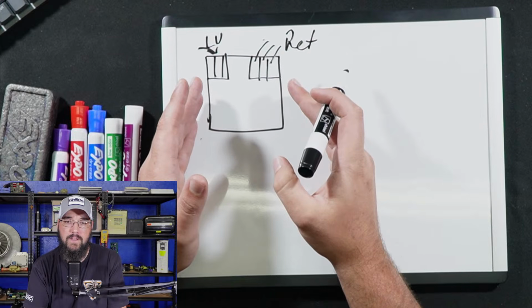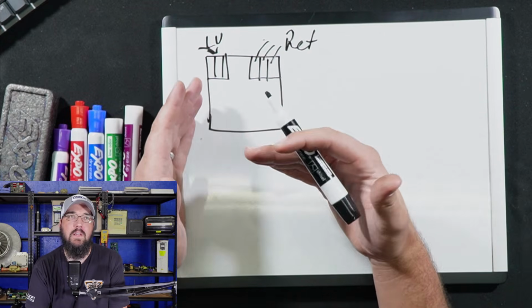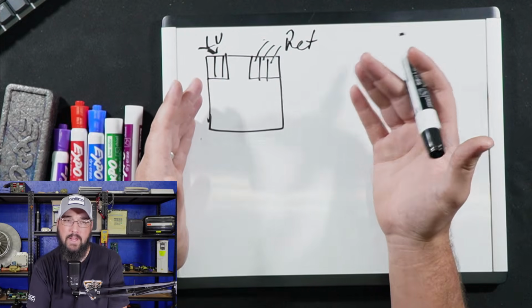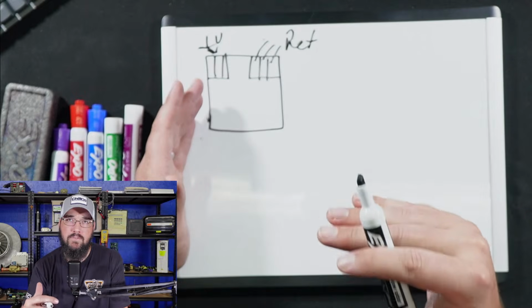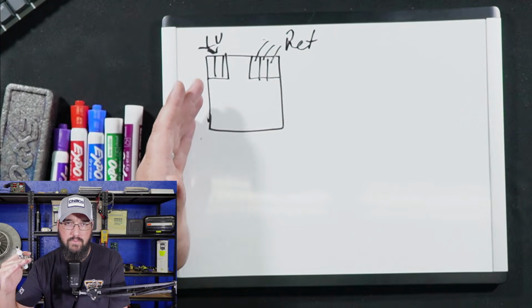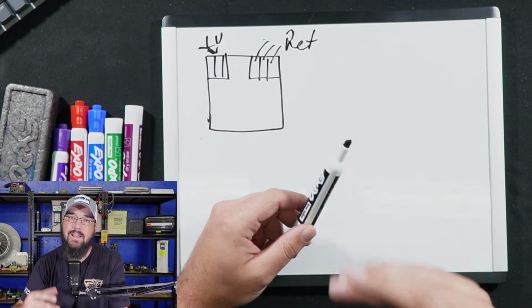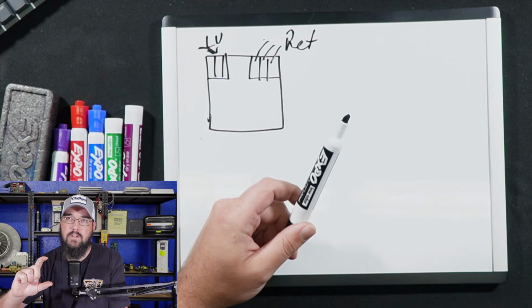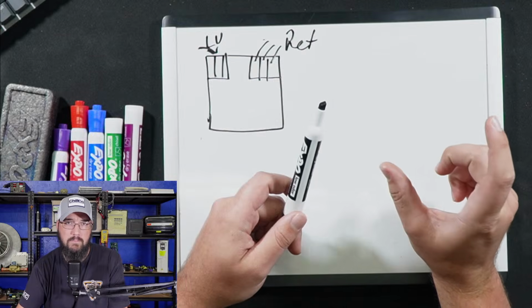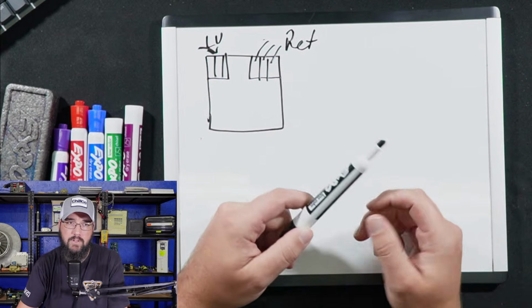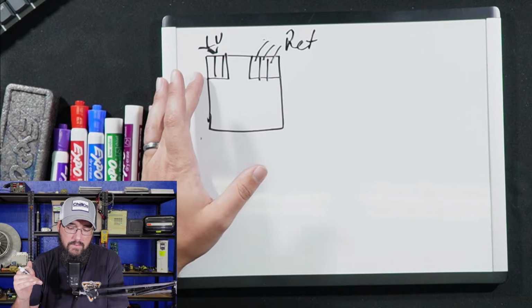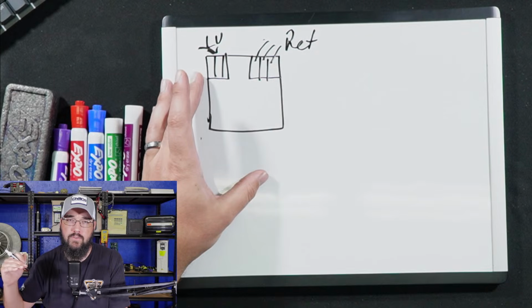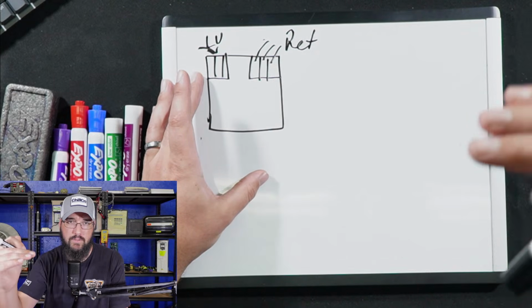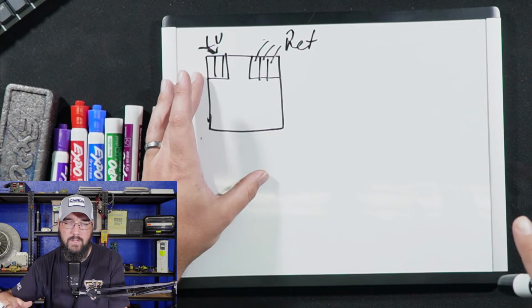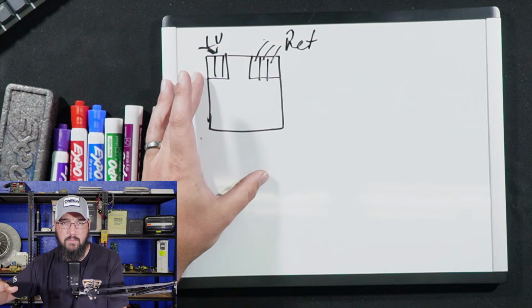because these are variable speed fans that are being controlled by typically the head pressure, that is the main thing the chiller is looking at. So it's going to monitor head pressure. Many of them will look at ambient as well. If we're above a certain ambient, let's just say 90 degrees Fahrenheit, it's very, very common for the fan control output to just go straight to maximum, which would be 10 volts DC in this particular case. And if it's below that, then the fans are going to slowly ramp as condenser head pressure builds. And then once it hits the condenser saturation set point, it will fluctuate or modulate the fan speed to maintain that head pressure.